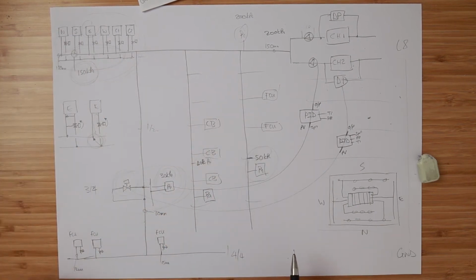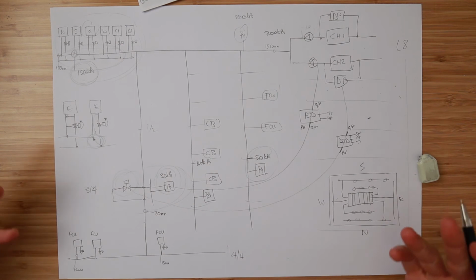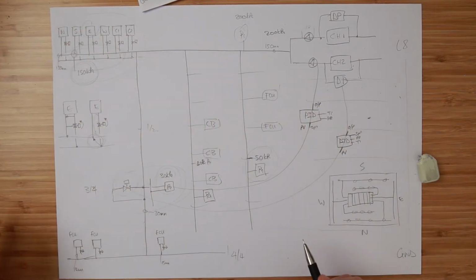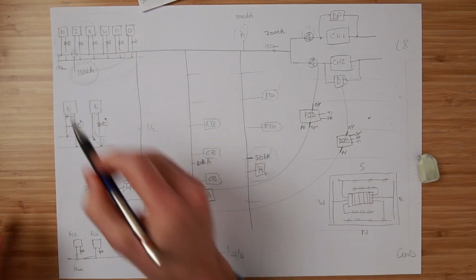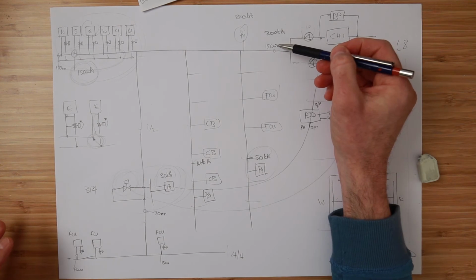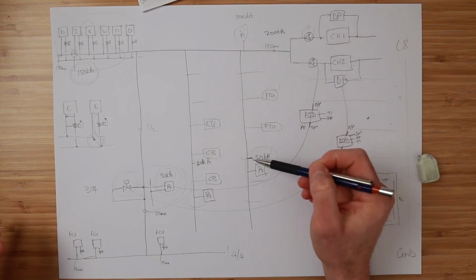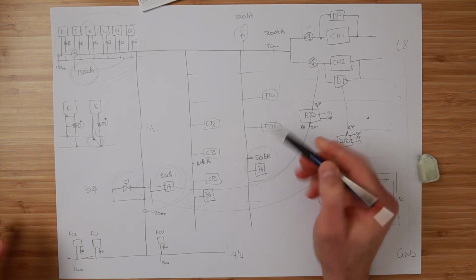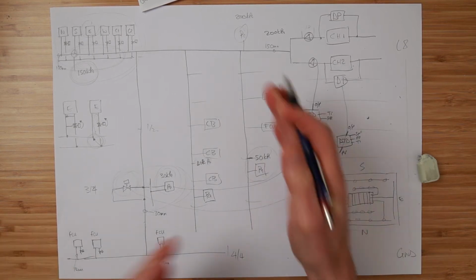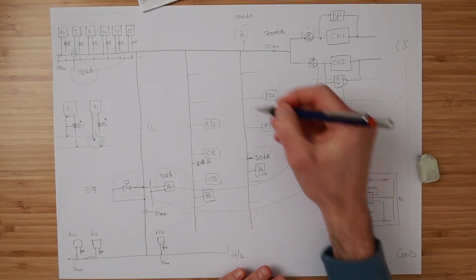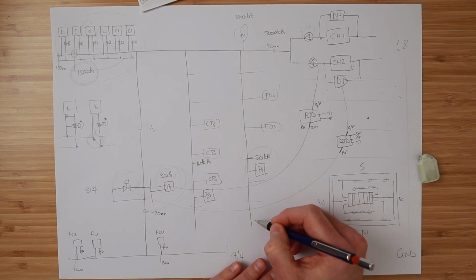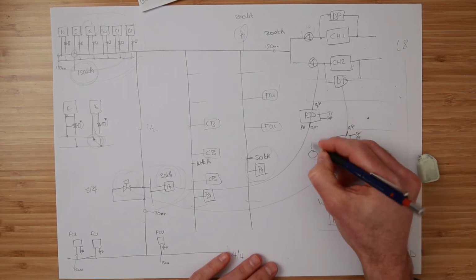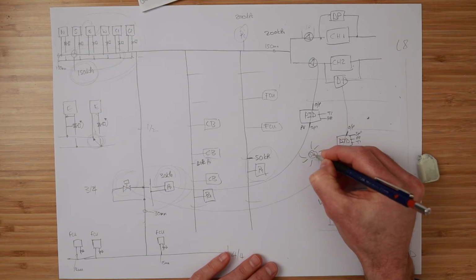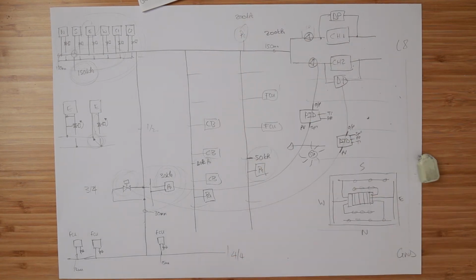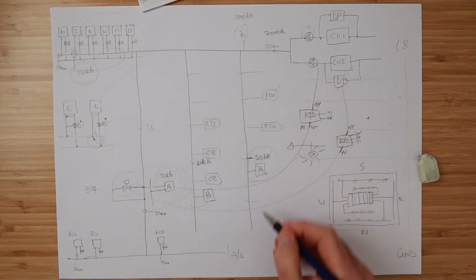And then what you would do is, when the system goes into automatic mode and everything's moving everywhere, you would look at all those pressures and maintain the speed of the pump to ensure that the lowest pressure was on set point. So if you're controlling to here, if this was the lowest one, these are all opening up. Let's say this is on the north side of the building here in Australia, and the sun is shining onto the north facade of the glass. These fan coils are going to be in full cooling maybe. So their chilled water valves are all fully open.